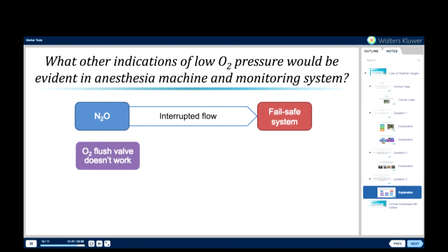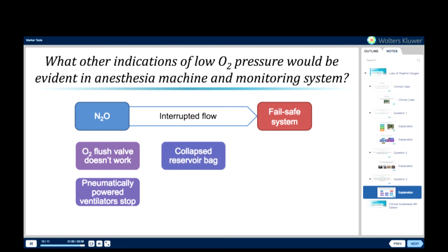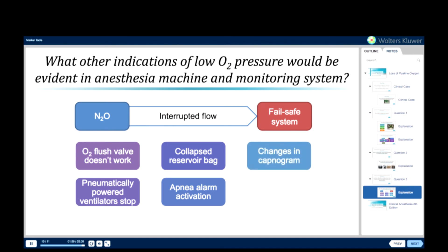The oxygen flush valve would not work, and pneumatically powered ventilators would stop working. Other consequences may include a collapsed reservoir bag, apnea alarm activation, changes in the capnogram, and a decreased oxygen saturation.